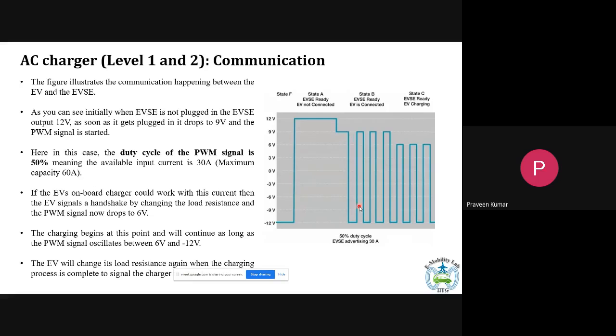Then the charger will send a 9 volt pulse at a duty ratio of, let's say, 50%. Take an example where the charger is capable of delivering 60 amperes of current - the charger still does not know how much current the battery can accept. So it sends a pulse with a duty ratio of 50% at the 9 volt level, meaning the charger is ready to deliver 30 amperes of current. Now the BMS knows the charger wants to deliver 30 amperes, since it's a 60 ampere charger and the duty ratio being sent is 50%.